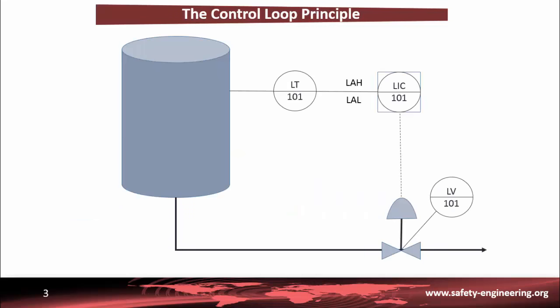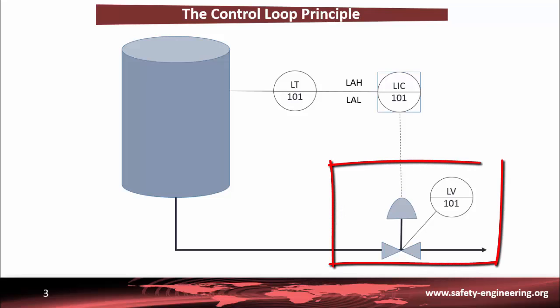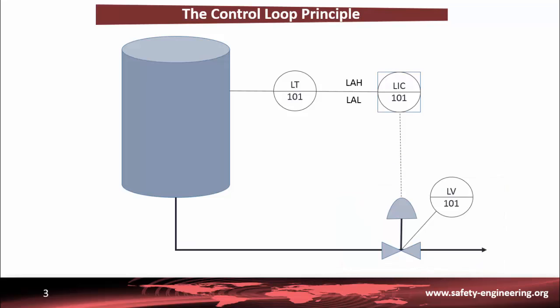Let's take a look at this figure. It's about a P&ID diagram. This figure shows a typical layout for the level control at the base of the column. The control valve should be placed on the discharge line from the pump. Let me show you the operating principle of this control loop. A level transmitter LT measures the level in the tank and transmits a signal associated with the level reading.